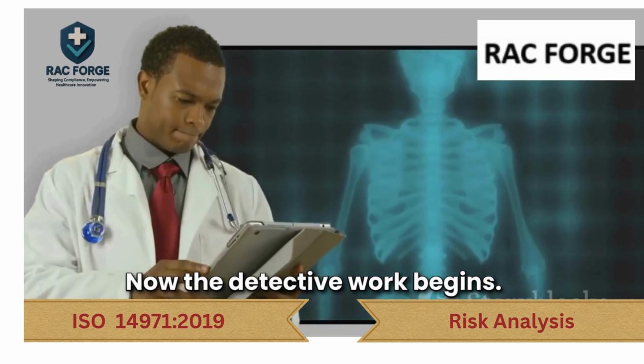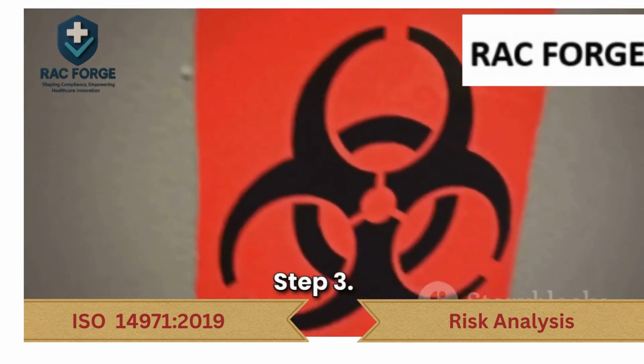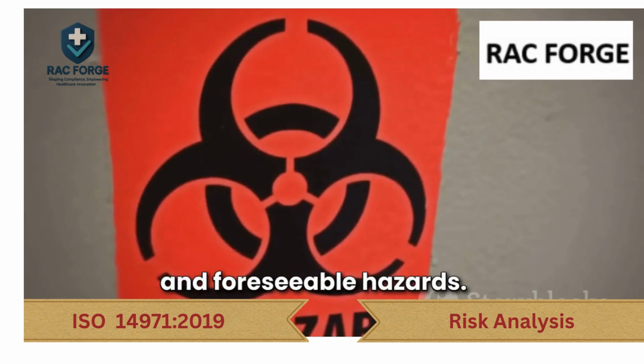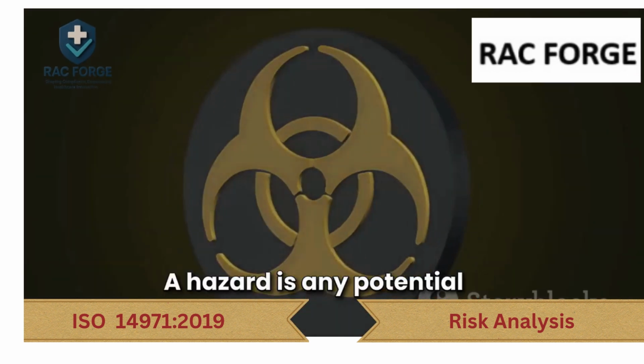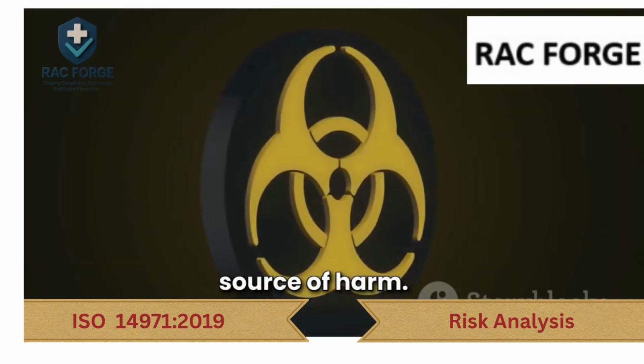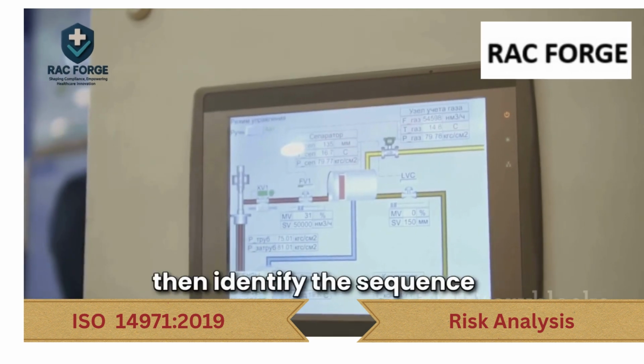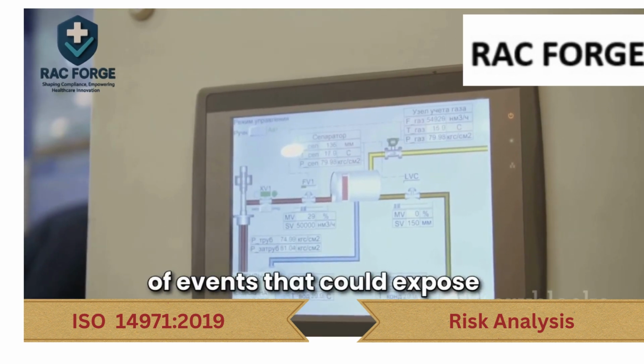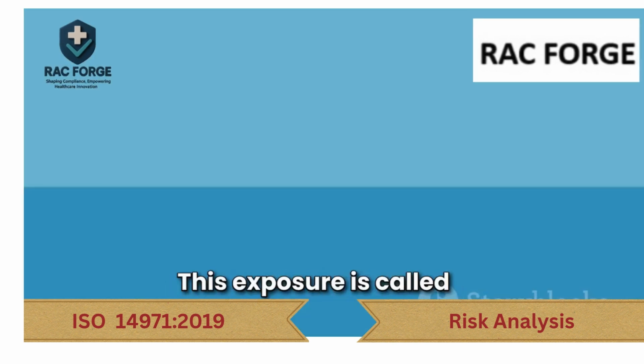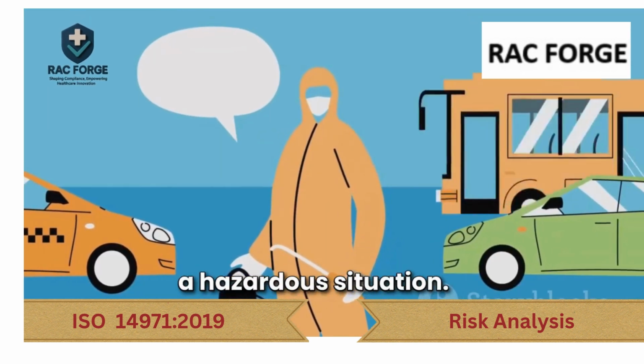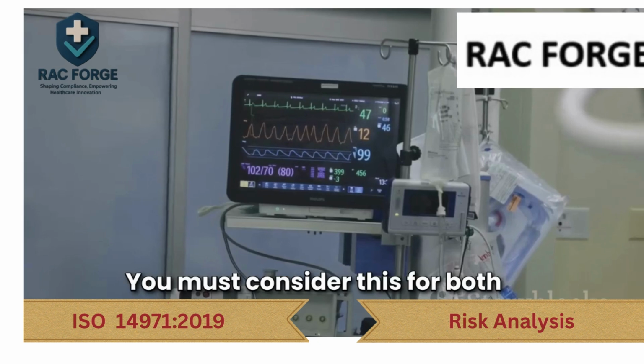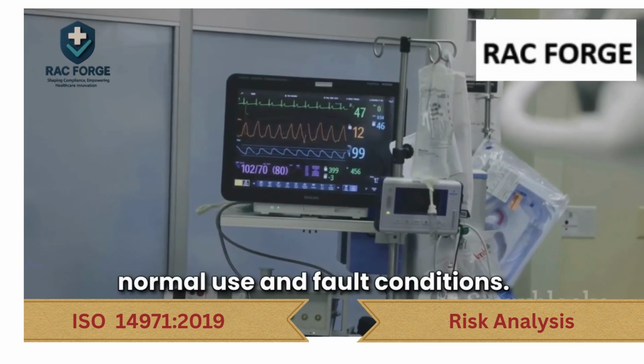Now the detective work begins. Step 3. Identify all known and foreseeable hazards. A hazard is any potential source of harm. For every hazard, you must then identify the sequence of events that could expose a person to that hazard. This exposure is called a hazardous situation. You must consider this for both normal use and fault conditions.